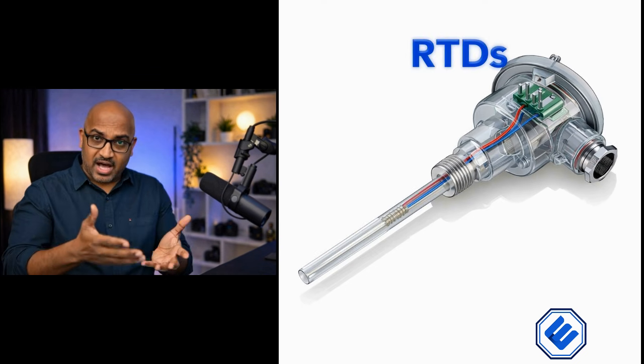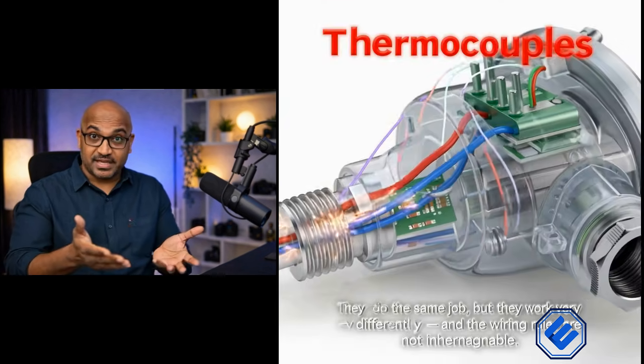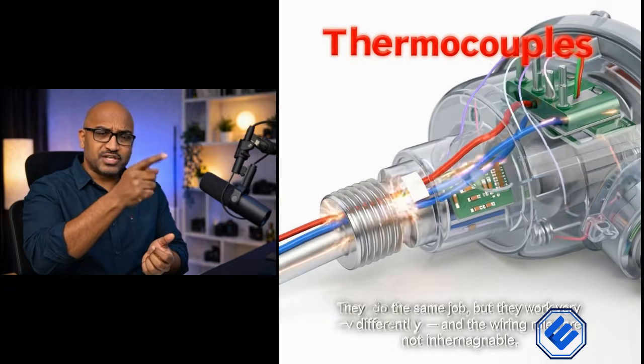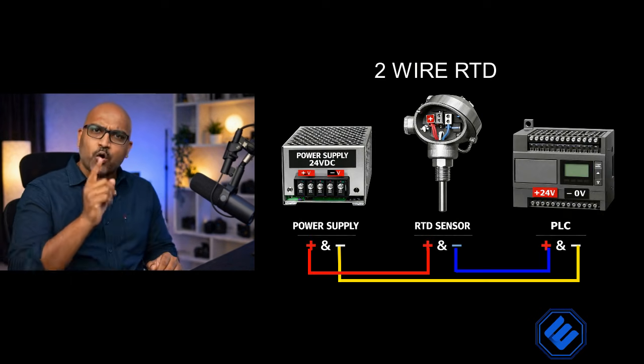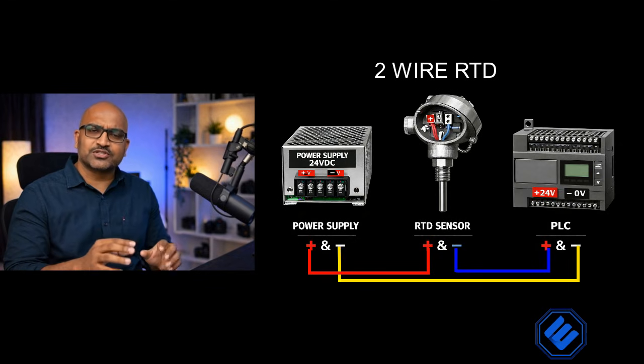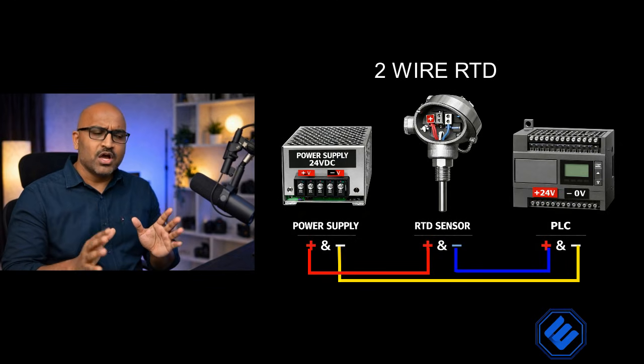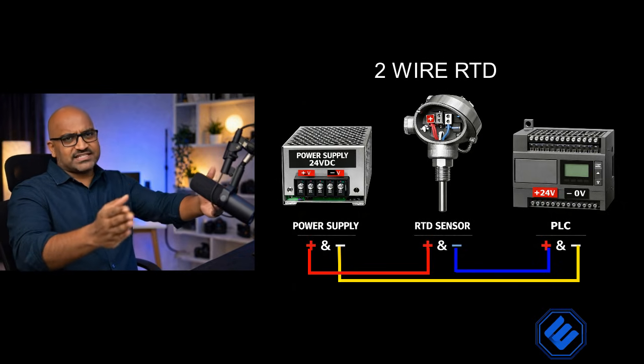Part 2. Wiring temperature sensors. Let's talk temperature sensors. Most of the time, you'll run into RTDs and thermocouples. They do the same job, but they work very differently, and the wiring rules are not interchangeable. An RTD works by changing resistance with temperature. The challenge? The wires themselves also have resistance. That's why we have different wiring options. 2-wire RTDs are the simplest configuration. They are also the least accurate. This is because there is no compensation for wire resistance. Only use this for short runs where accuracy isn't critical.